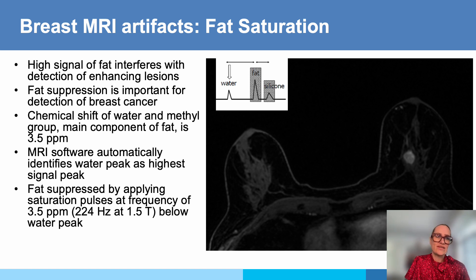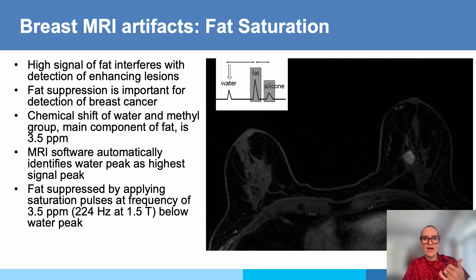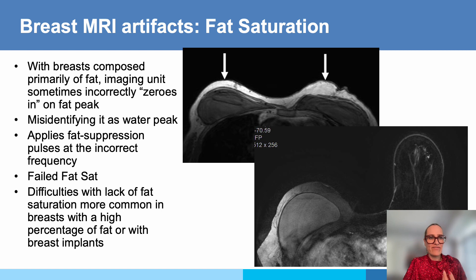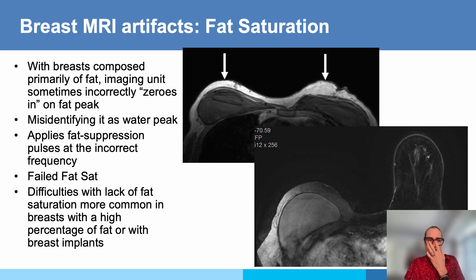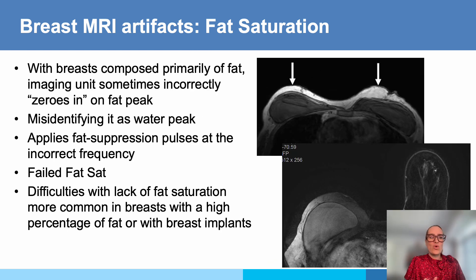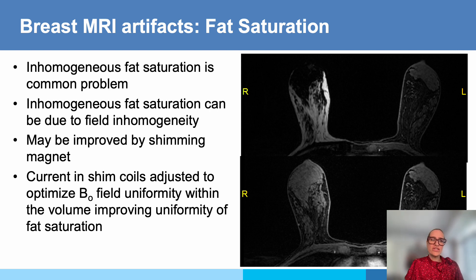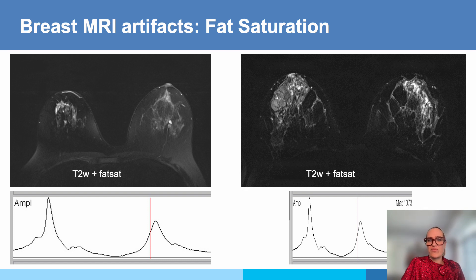The most important technical issue is inadequate fat suppression. The MRI software automatically identifies the water peak as the highest signal, but if fat is predominant in the breast it can happen that the wrong peak is identified. The technologist will identify this and can correct it by manually selecting the peak — this is especially pronounced when one breast has an implant and the other is normal glandular tissue. Inhomogeneous fat suppression is a common problem but can be improved by shimming the magnet; shim coils adjusted to optimize B0 field uniformity within the volume improve fat saturation uniformity.